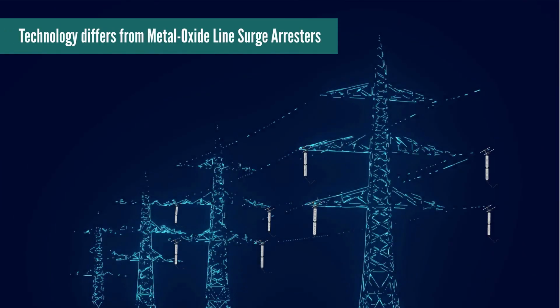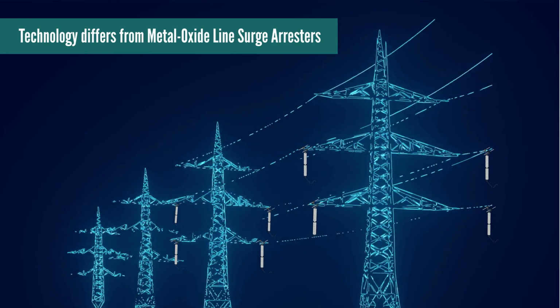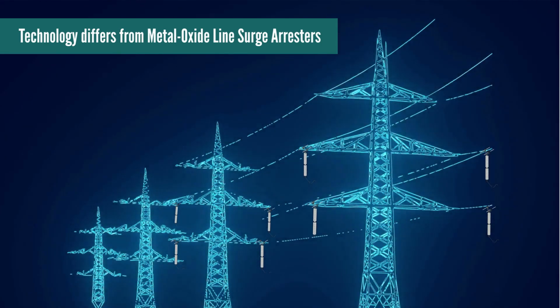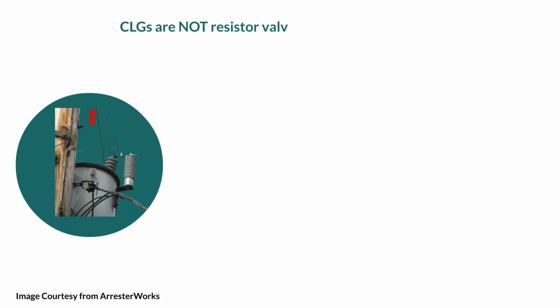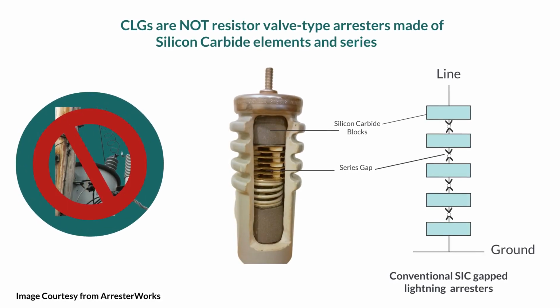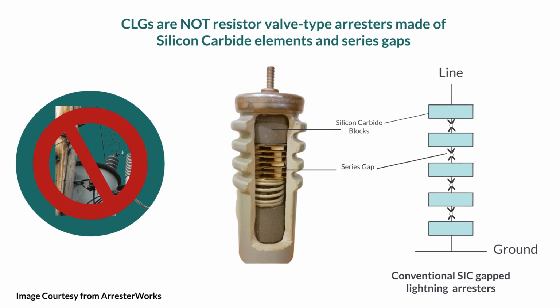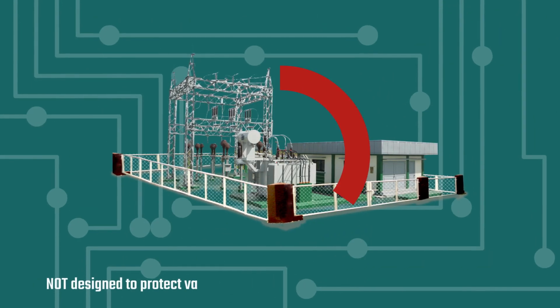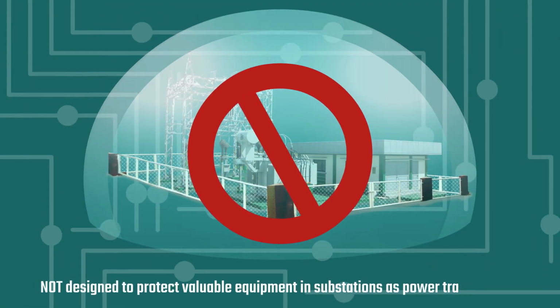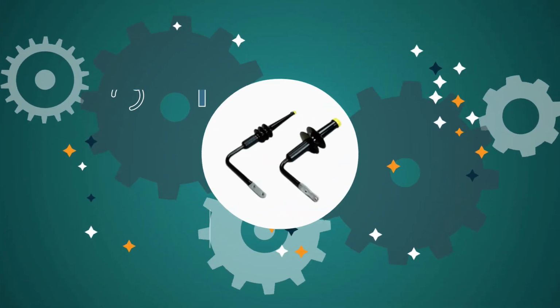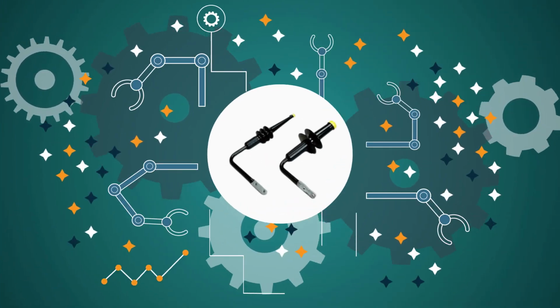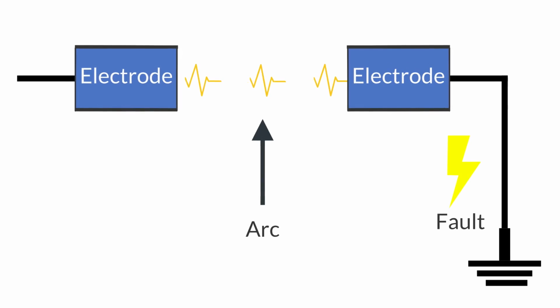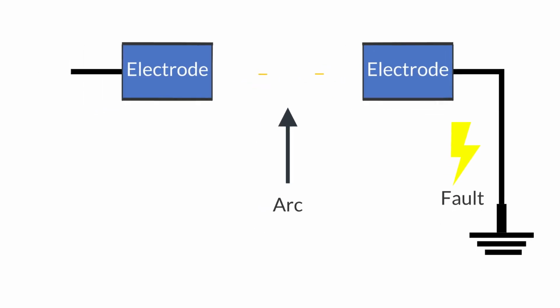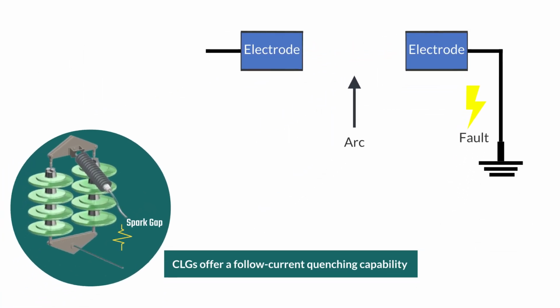Nevertheless, their technology differs from Metal-Oxide Line Surge Arresters, commonly used on transmission systems. CLGs are not resistor valve type arresters, made of silicon carbide elements in series gaps. They are not designed to protect valuable equipment in substations such as power transformers. CLG technology uses an innovative approach made of one or several arc quenching chambers. CLGs offer a follow current quenching capability that is verified in a similar way to externally gapped line arresters, e.g. EGLA.